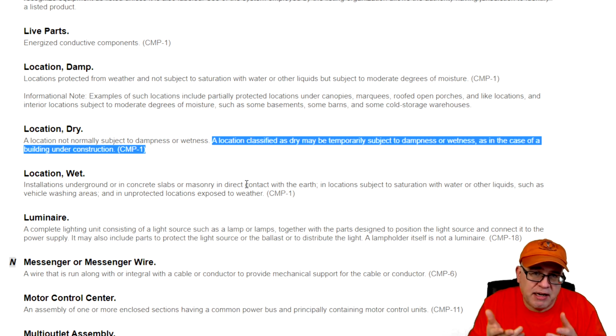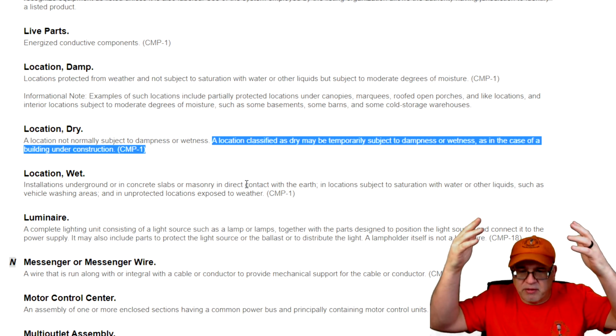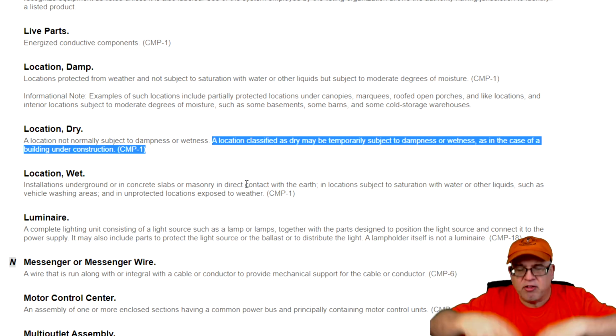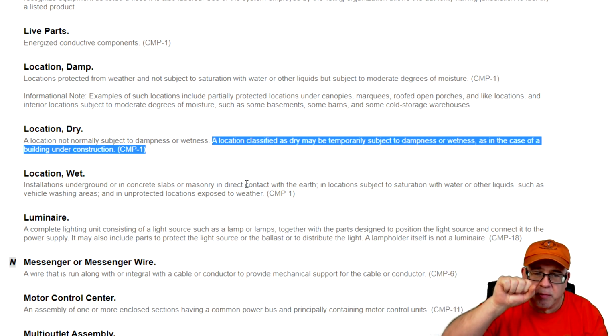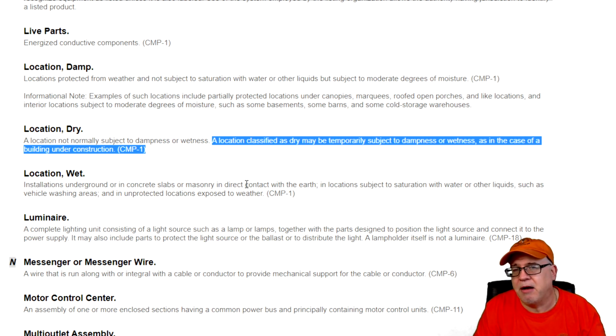If it was saturated and flooded and it sat underwater long term, then I'm going to tell you to take it out because I don't know what was in that water. If it was gravitationally applied, like with a sprinkler system, it just hits some of it and then it runs off of it, it's not suspended or submerged, then I'm going to say no harm, no foul. So again, the conditions of use will vary.